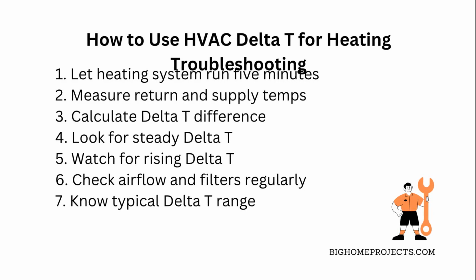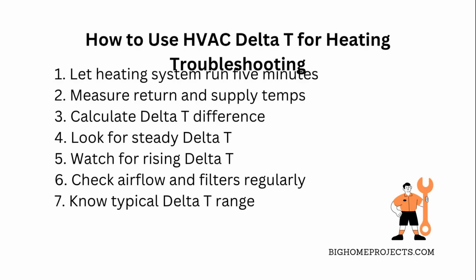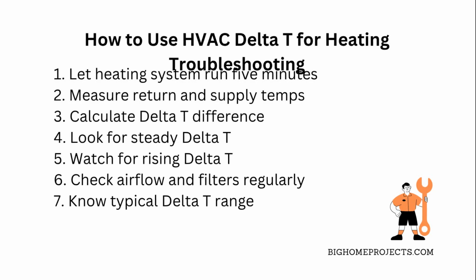Subtract the return temp from the supply temp. That number is your Delta T. Ideally, this difference should stay steady while the system runs. If it keeps climbing, that's a red flag.